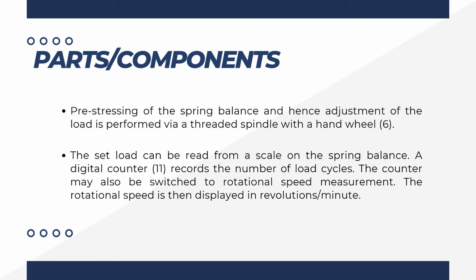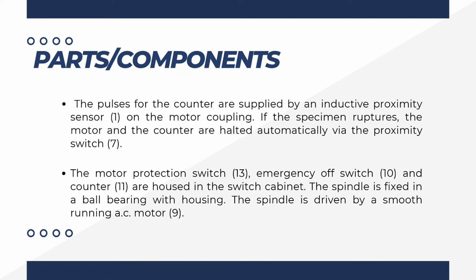Loading of the specimen is performed using a spring balance and the floating bearing. Pre-stressing of the spring balance and hence adjustment of the load is performed via a threaded spindle with a hand wheel. The set load can be read from a scale on the spring balance. A digital counter records the number of load cycles. The counter may also be switched to rotational speed measurement. The rotational speed is then displayed in revolutions per minute.